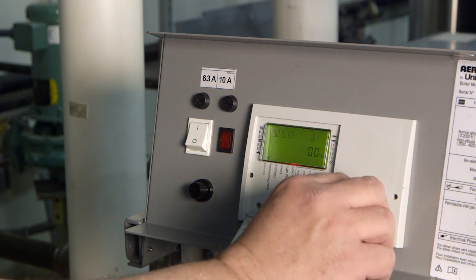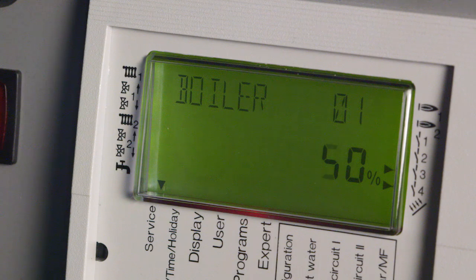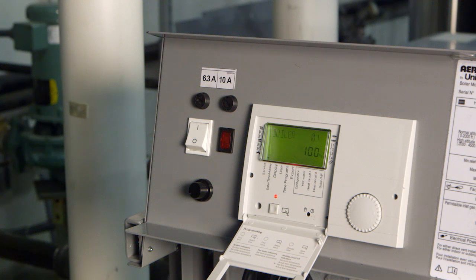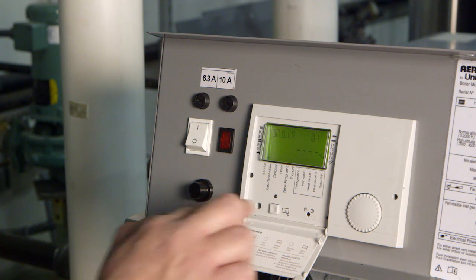By turning the wheel as shown, you can increase or decrease the value per boiler by 10% with a maximum value of 100%. When you've reached the value you want for the boiler, hit this button to confirm the amount. Please note that this function is active for 15 minutes at a time. After this time is up, the system will automatically default back to previous run mode. If service mode times out, simply return to the service mode, reset the Cascade Manual setting, and resume calibration.